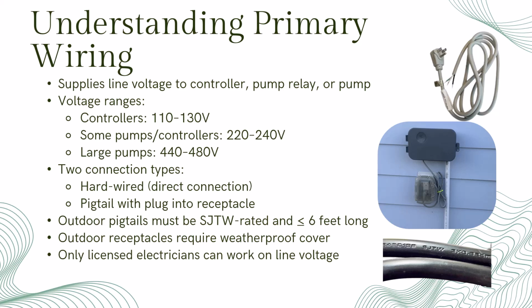Just make sure the pigtail is rated SJTW and no longer than 6 feet. If it's outside, it must be plugged into a GFCI outlet with a full-time weatherproof cover. And remember, any work involving line voltage must be done by a licensed electrician. It's not just about following code, it's about safety.